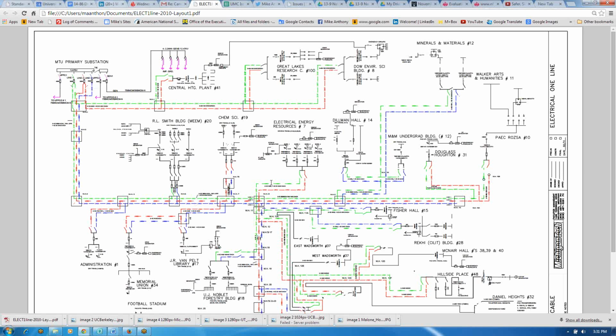I should mention I also did an arc flash analysis on the electrical equipment, mains, and so forth, and got that labeled throughout most of the buildings. So do you have any incident energy that would require PPE greater than category 4? On some, like 2,000 kVA transformers and the first main subfeeds, I found levels beyond 4 — danger level — so we have to shut them down to do any work.